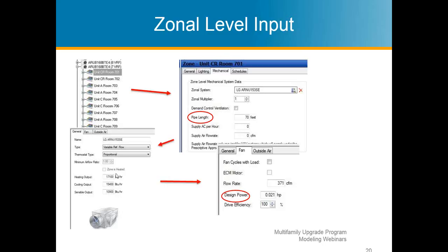On the general tab, you're going to be putting in all the heat output and cooling output, sensible output information of that one system. You're going to click over to fans, and in the fans, you're putting in your flow rate of that CFM, your design horsepower, and then the drive efficiency of that system. So that's the zonal level, and then obviously underneath that is your room and your room information, your walls, your windows, all that good stuff, envelope components.